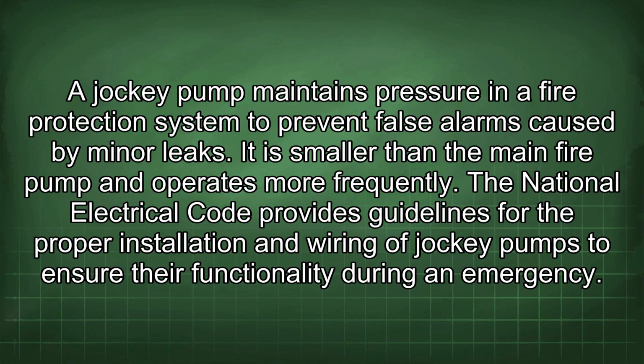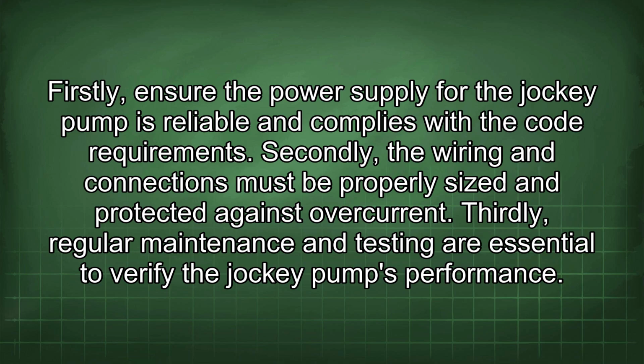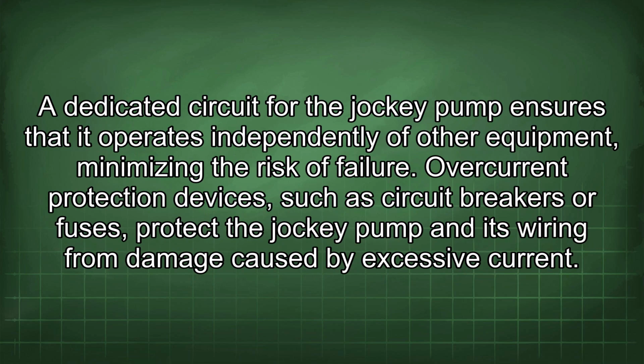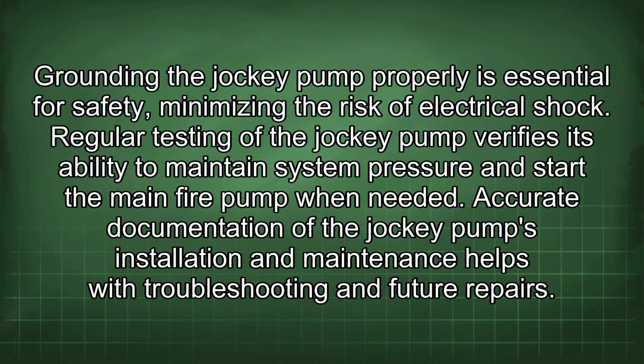an emergency. Firstly, ensure the power supply for the jockey pump is reliable and complies with the code requirements. Secondly, the wiring and connections must be properly sized and protected against overcurrent. Thirdly, regular maintenance and testing are essential to verify the jockey pump's performance. A dedicated circuit for the jockey pump ensures that it operates independently of other equipment, minimizing the risk of failure. Overcurrent protection devices, such as circuit breakers or fuses, protect the jockey pump and its wiring from damage caused by excessive current. Grounding the jockey pump properly is essential for safety, minimizing the risk of electrical shock.